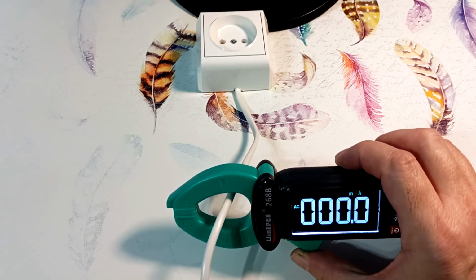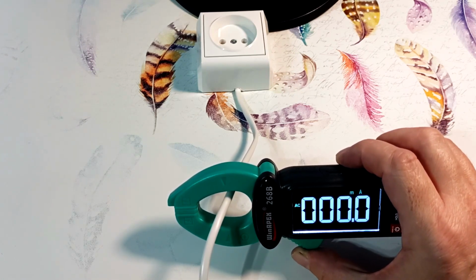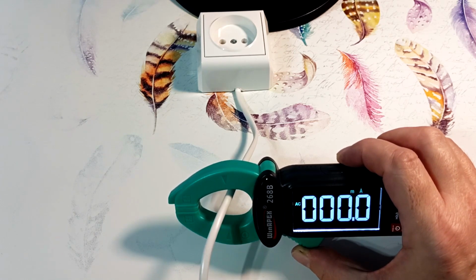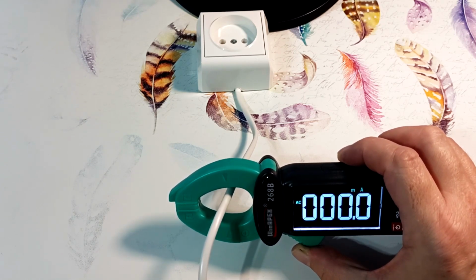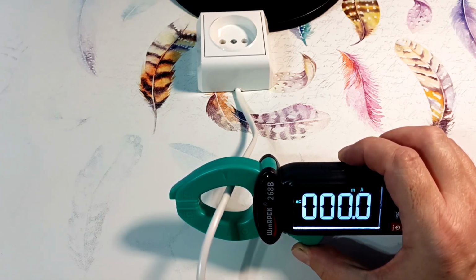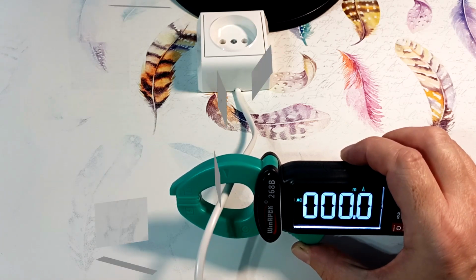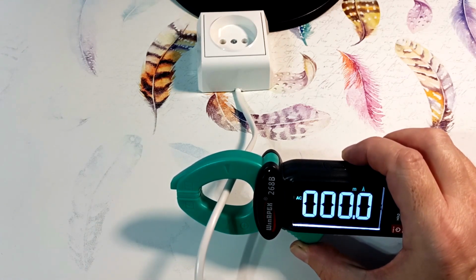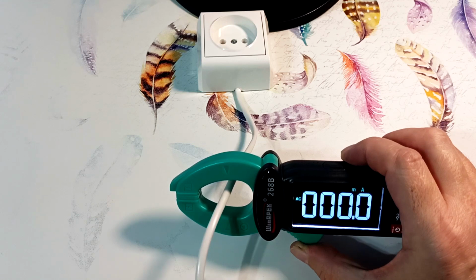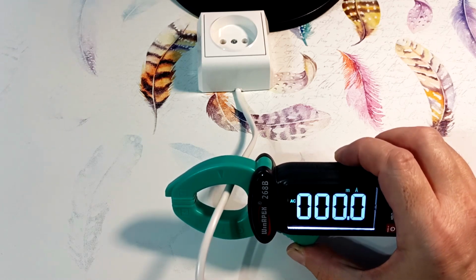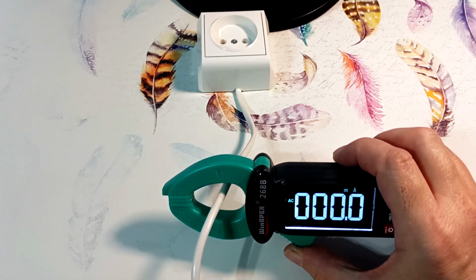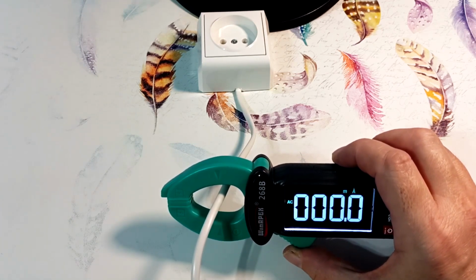The same device can be used to search for leaks in three-phase circuits. We simultaneously connect three-phase clamps and a neutral wire, and measure the leakage current in the load. We can also use the device to check the symmetry of the load in a three-phase circuit. By clamping three phases without a neutral wire in pliers, the device will show the unbalanced current.